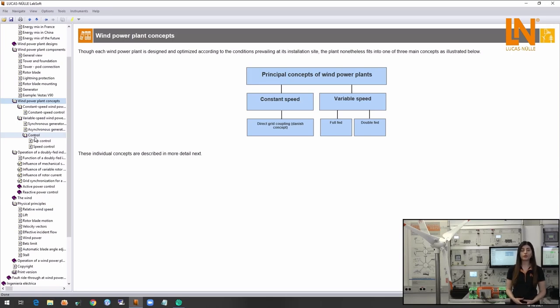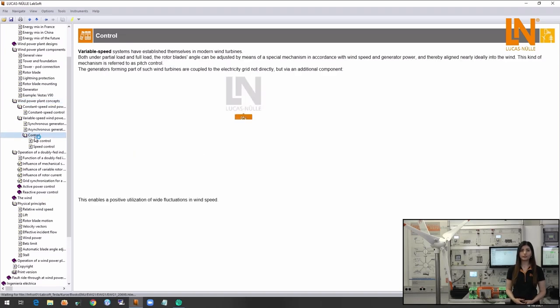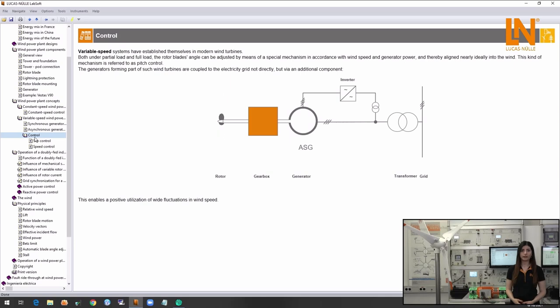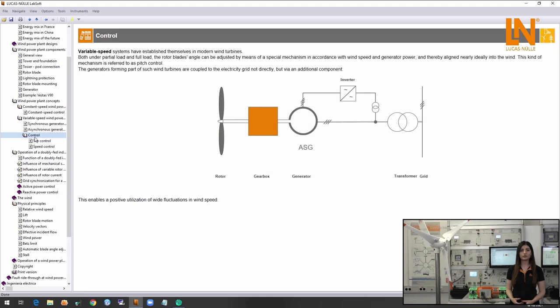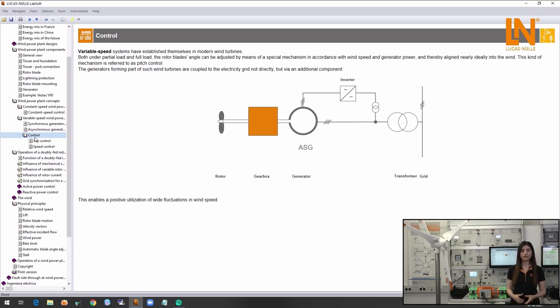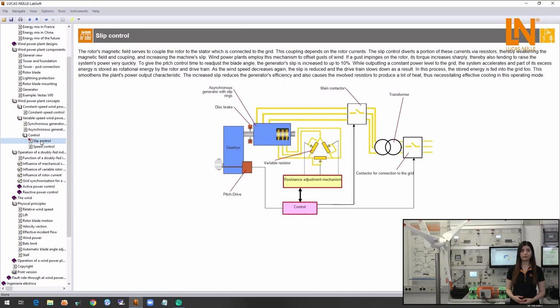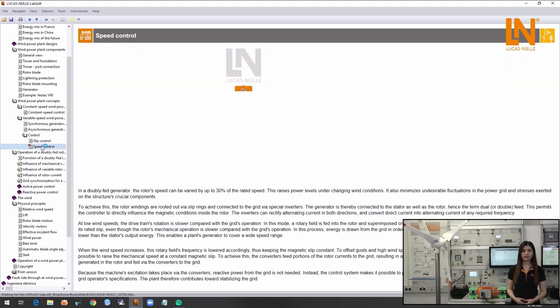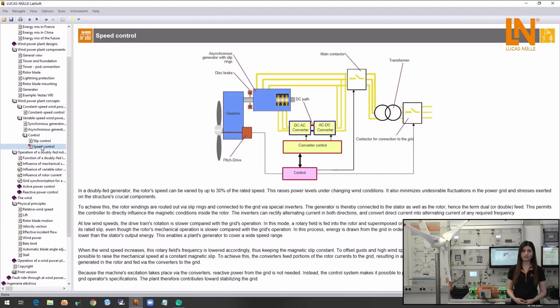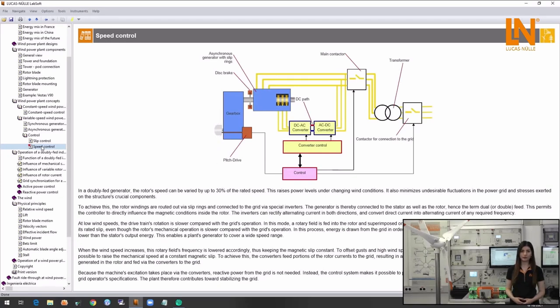Here we are going to focus on the double fed induction generators which are widely used in the wind power plants. In this concept we can utilize wind energy in an efficient way by means of the variable speed generator and the frequency converter. The wide range of control strategies in the variable speed systems has allowed them to establish themselves in modern wind turbines. The special advantage of this concept is the ability to control the active and reactive power for grid stabilization.